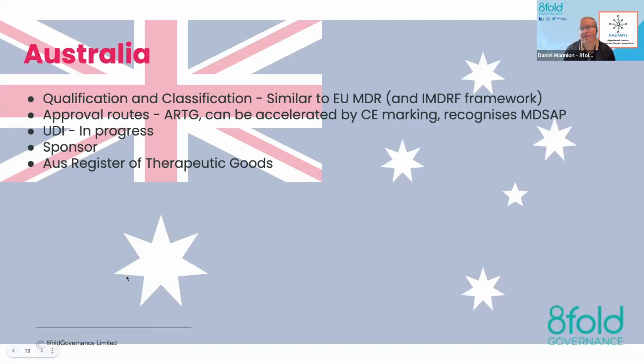Australia, again, has similar qualification and classification criteria to EU MDR. Their approval routes are through the Australian Register of Therapeutic Goods, and the approval can be accelerated if you're already CE marked. So if you have a CE mark for an EU MDR product in the EU, getting into Australia is a lot easier. Australia are also part of MDSAP, so while they don't require MDSAP, they will recognize an MDSAP certificate as covering your quality management system. They're in transition for UDI, so you may not need a UDI at initial registration, but you will in the next couple of years. You require what's called a sponsor in Australia, which is a local representative for Australia, and the database is called the Australian Register of Therapeutic Goods.